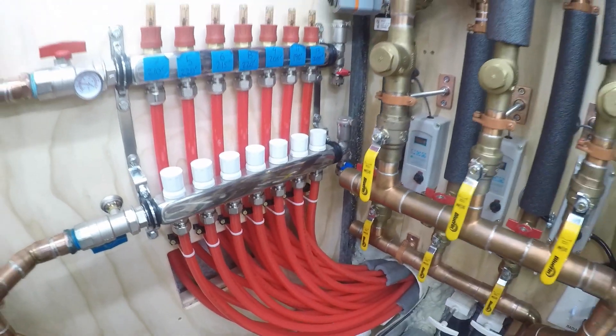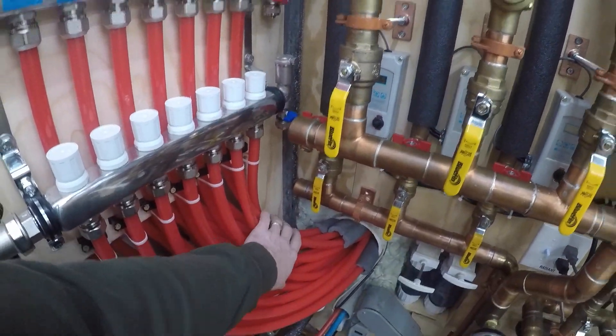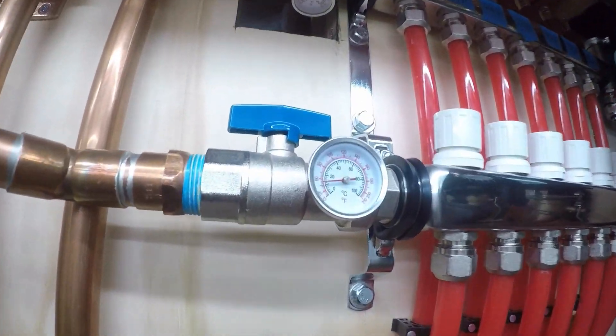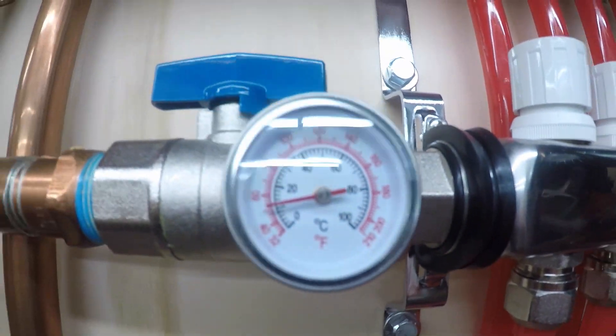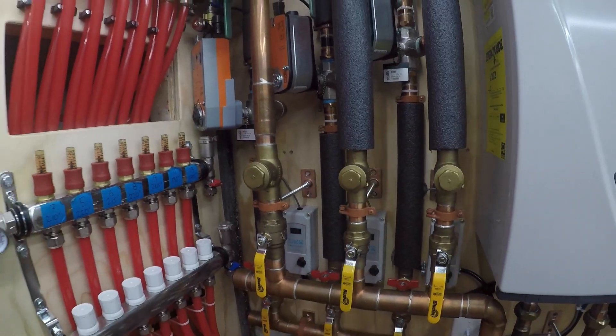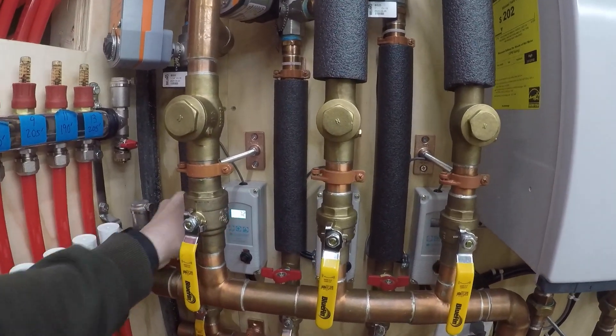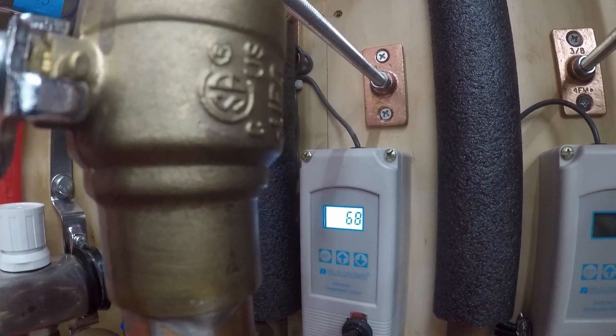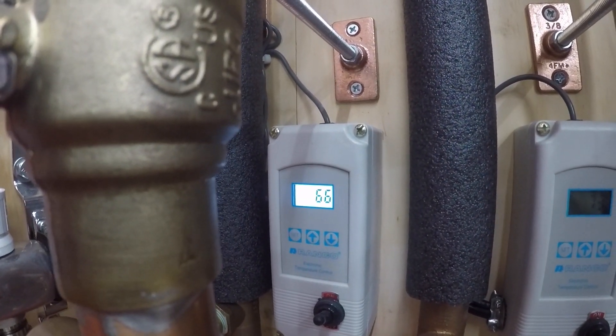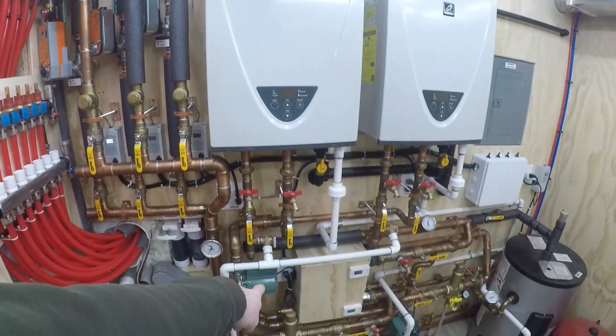Okay, pump is on. You'll start to hear the PEX click — that's just the expansion and contraction of the PEX itself moving and rubbing against each other. It only happens because the temperature is dropping so quickly. We're showing 75, 74, 73, 72.